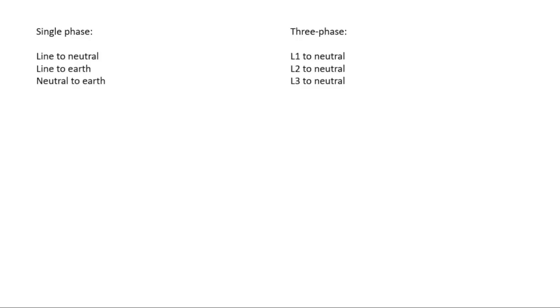I've stated that in single phase applications we test line to neutral, line to earth and neutral to earth. In a three-phase environment there are 10 tests to perform, namely L1 to neutral, L2 to neutral, L3 to neutral, L1 to earth, L2 to earth, L3 to earth, L1 to L2, L1 to L3, L2 to L3 and neutral to earth. If all three phases have been isolated, then there should be no voltage readings in any of the above test combinations, but remember to verify your voltage testing instrument afterwards.